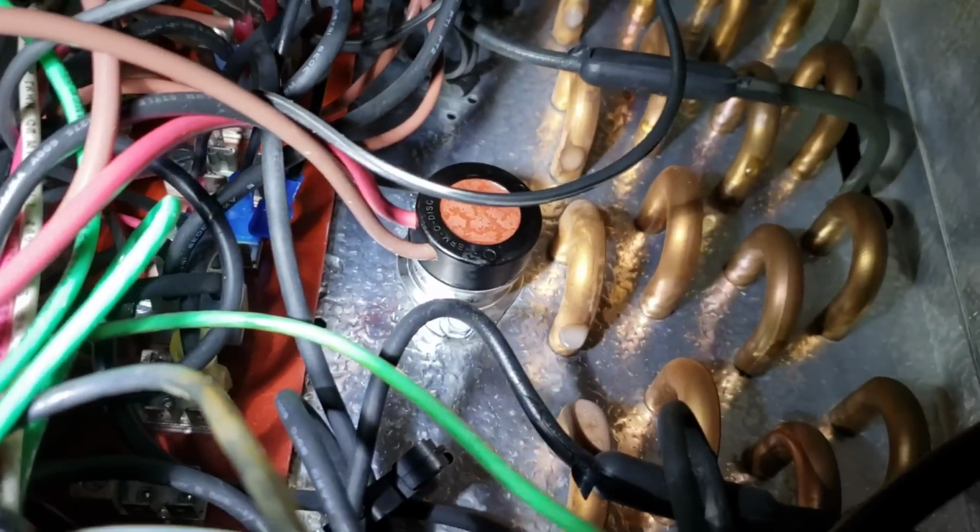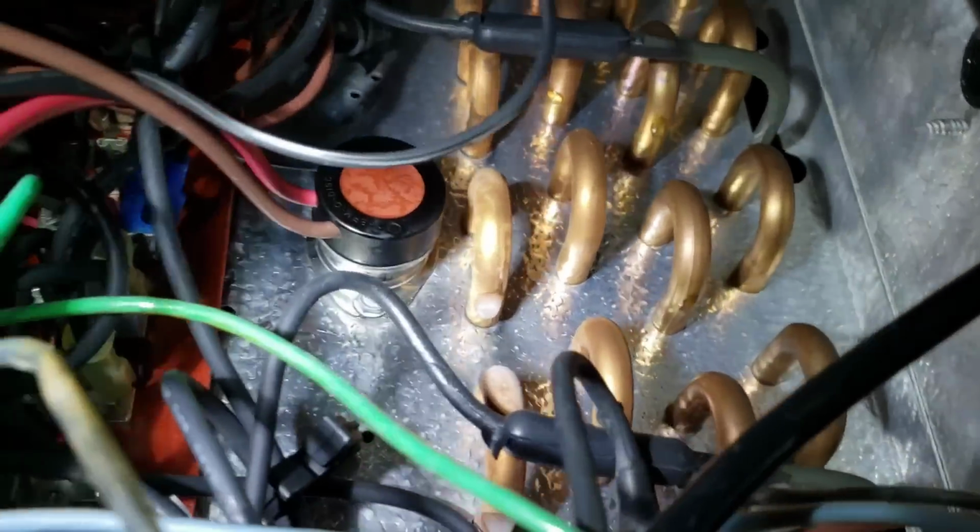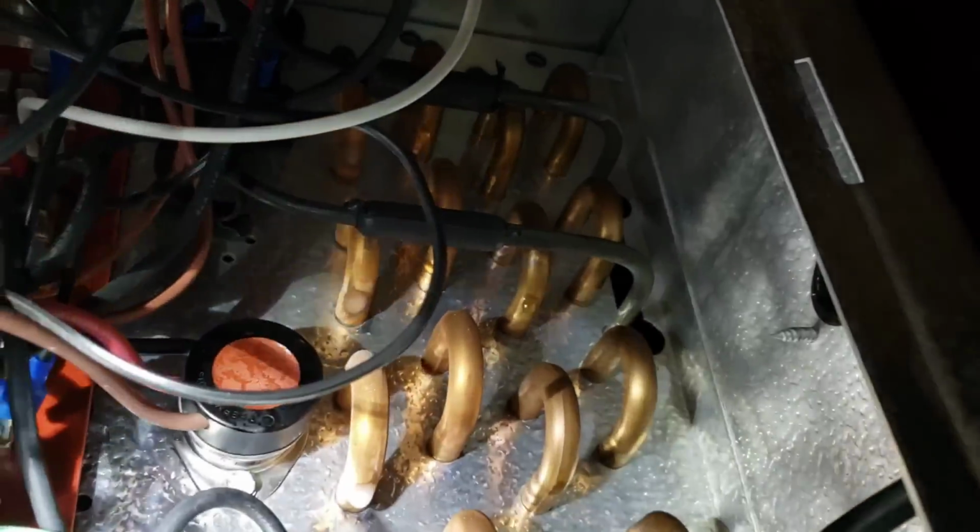So there's a little bit of gap too on our 3-wire switch, our defrost termination fan delay switch right there. I can't really get to an angle where I can show you guys. Maybe over here. Yeah, not really, no. But around the black part of that, where it just goes into the metal part, there's a bit of a gap in there as well. So I'll probably add that to my quote of things to do.